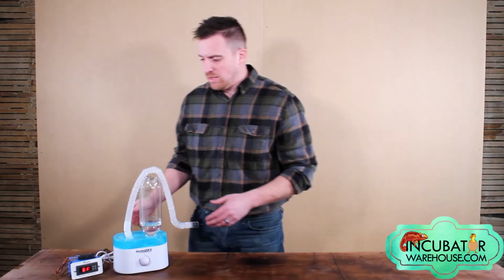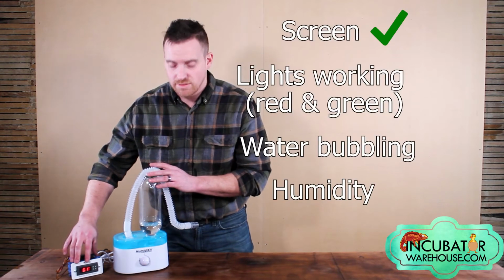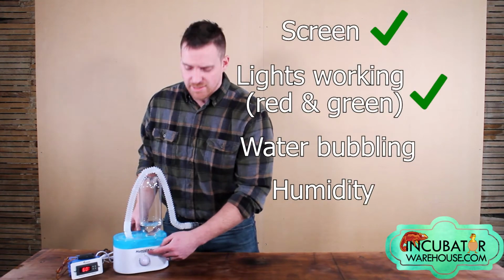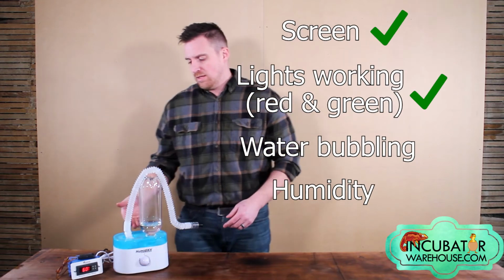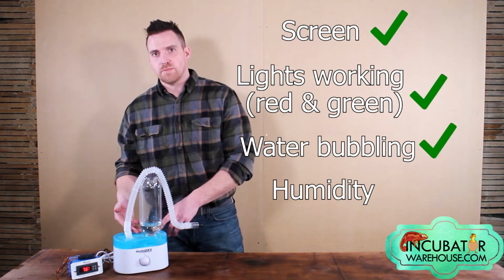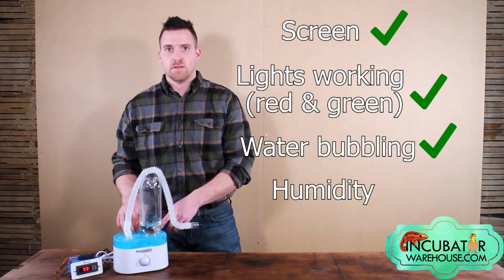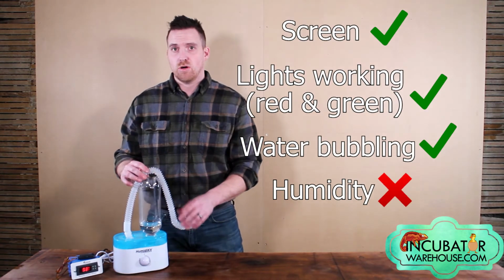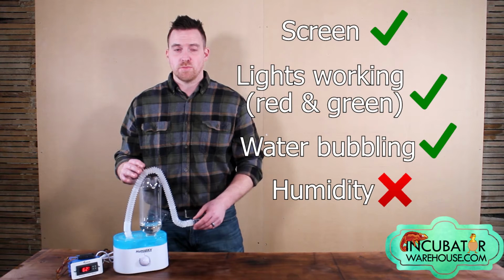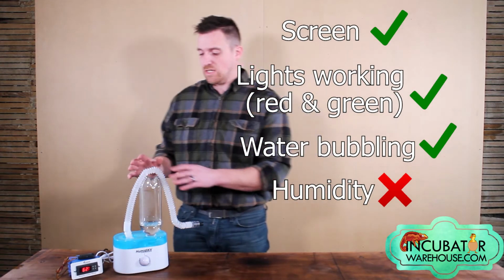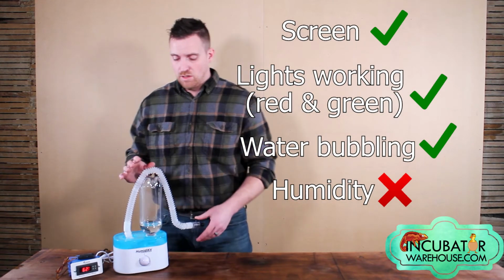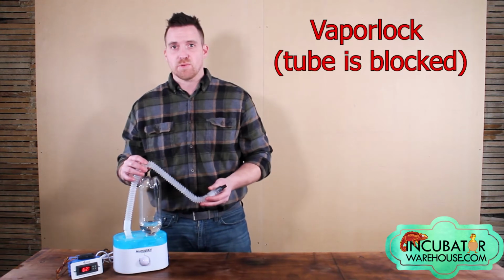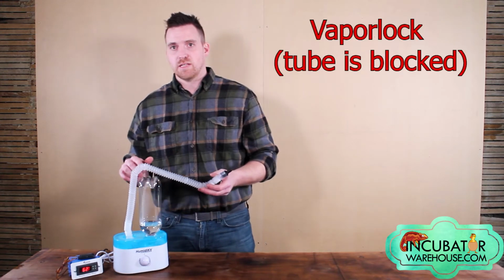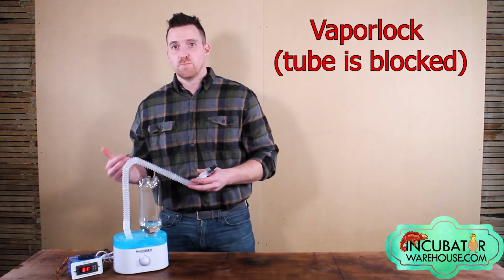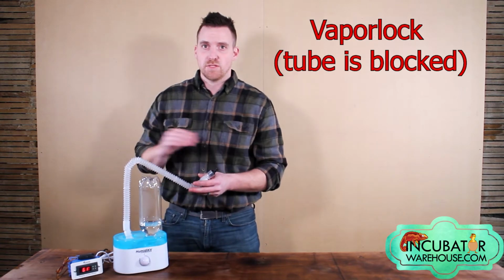One of the problems that we often encounter with the Humidikit is customers say the screen is on, the indicator lights are both functioning, red and green, and water is bubbling, producing humidity on the inside of the base. Yet, no humidity is produced through the tube. There's two simple solutions that can help alleviate this problem. The first one might be you're experiencing Vaporlock, where you have water bubbles building up inside the tube, blocking your mist from passing through the tube to the incubator.